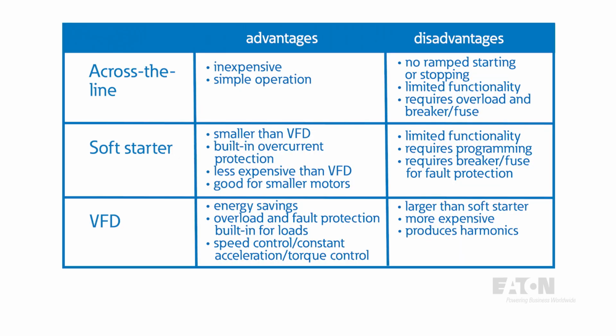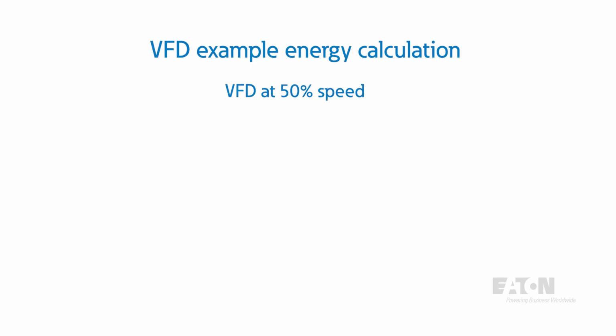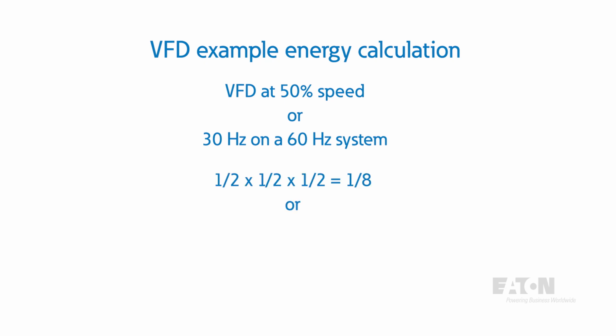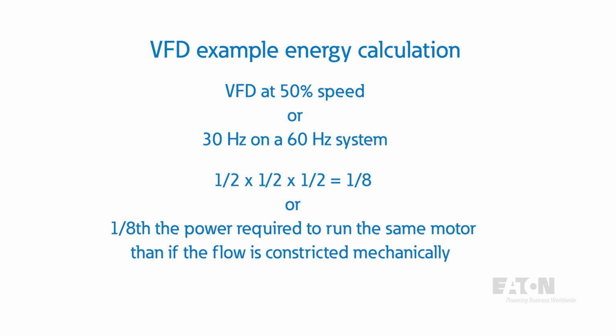The advantages and disadvantages of each motor starting and control technique are summarized in this table. Beyond their benefits for motor starting, VFDs can offer significant energy savings depending on the application. In general, the energy savings are a cubic function proportional to the speed. For example, if you operate at 50% speed or 30 Hz on a 60 Hz system, the motor would only use a half times a half times a half, or 1/8 of the power required to run the same motor if you constricted the flow mechanically.